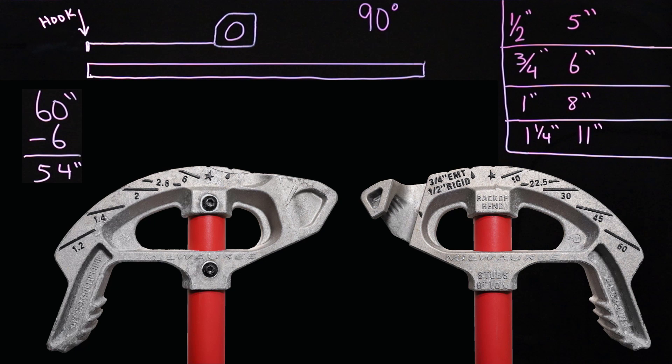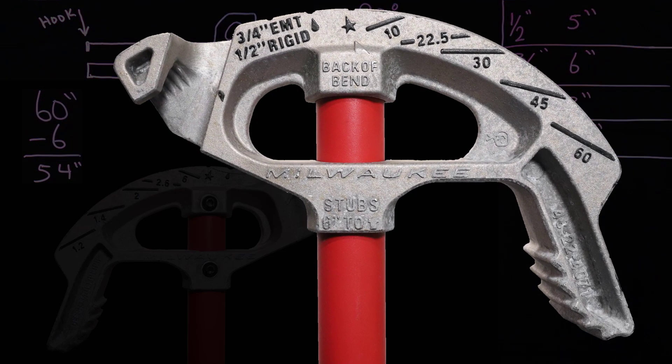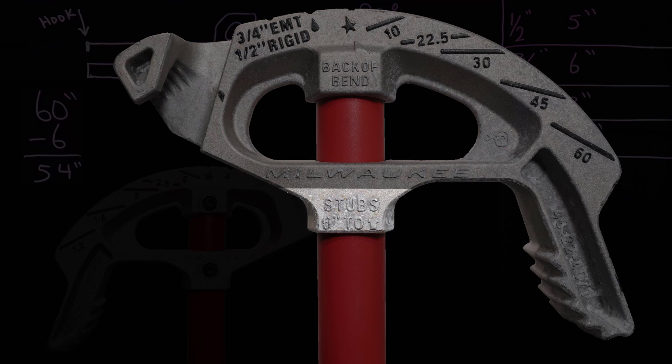Now, some of these benders may have a little bit difference, especially on the inch and a quarter. So always read your bender. The bender head will tell you what the deduction is. There's a different manufacturer that does something a little bit different than the 11 inch. So make sure you read it. It's right on the head of the bender. Always read that.